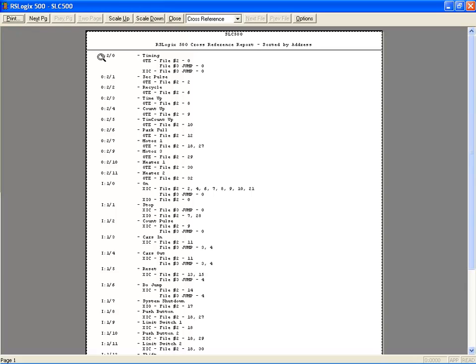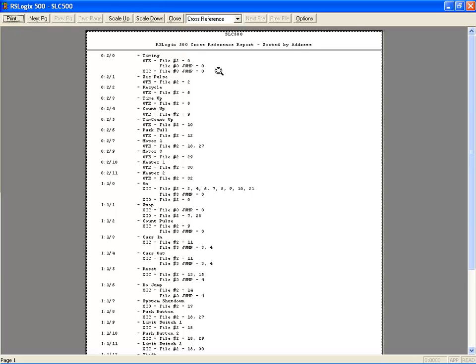Cross-reference shows the instruction and the rung number it's on and the file number it comes from. Here we are looking at the timing output of the file O.2.0. It's located in ladder file 2 rung 0, ladder file 3 rung 0, and it's using an output energizer and an XIC. So you can see if you go through the cross-reference, you can find where in your program a particular instruction lives and its name. Very handy for sorting complex programs.